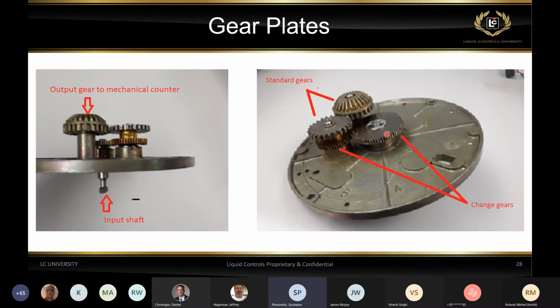In this case, only 2 of them. They change gears because, well, they change. There are different numbers of gears, there are different sizes of gears, and a combination of those gears creates a specific ratio, allowing us to drive the counter with the right speed, accurately displaying whatever units of measure we're looking for. So we have standard gears, and then we have change gears.